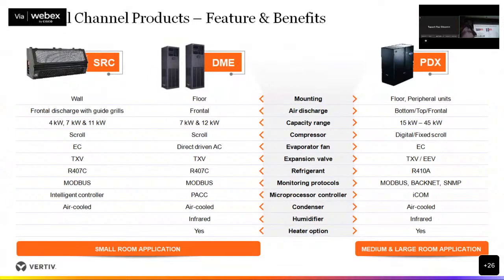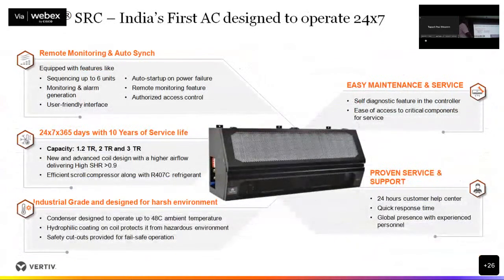Because temperature and RH are inversely proportional: whenever your temperature rises, humidity comes down. So if you control the temperature precisely, your humidity is automatically maintained in a closed control room, if you don't have a leakage within the room. And second, by default it comes with the Modbus communication protocol, where you can integrate this device with your BMS and monitor.